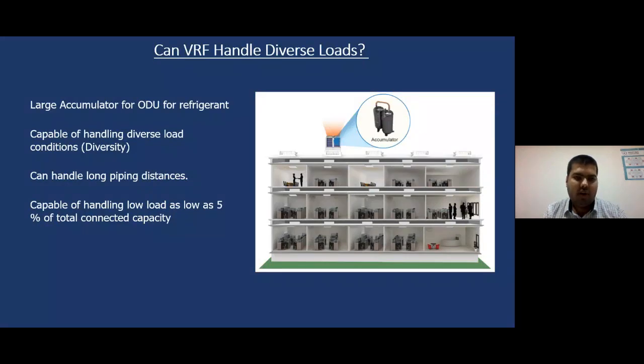VRF is also capable of handling diverse load conditions. There's a factor called diversity in VRF, which you would mostly hear from air conditioning people. So what basically is diversity? Suppose I have a requirement of 6 tons of load. The air conditioning contractor would install 6 tons of indoor units, but only 4.5 tons of outdoor. The ratio of 6 by 4.5 is basically the diversity of that VRF system.